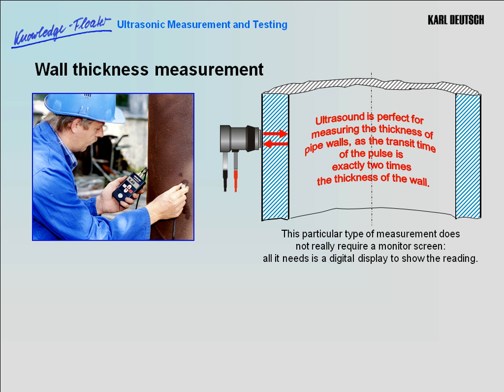Wall thickness measurement. Ultrasound is perfect for measuring the thickness of pipe walls, as the transit time of the pulse is exactly 2 times the thickness of the wall. This particular type of measurement does not really require a monitor screen. All it needs is a digital display to show the reading.